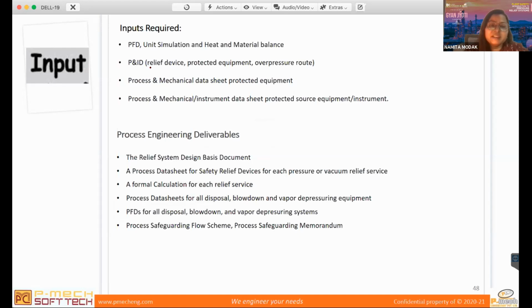Then you need the P&IDs, just to do the detailing of those PSVs. Then the process and mechanical data sheets. And what are your deliverables? The relief and blowdown summary is a document which we normally prepare plant-wide, where we list all the PSVs or BDVs, which are blowdown valves, in your system. So that is one of the deliverables.